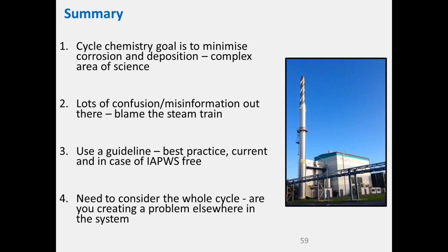There's a lot of misinformation and confusion out there, and I blame the steam train for that, but also some of that comes into what's right for one design and pressure of boiler is not necessarily right for another. So you've got to understand the cycle. And I recommend use a guideline, best practice, current, take a free one from IAPWS, or you can look at purchasing the ASME one and things like that. And you need to consider the whole cycle. By doing one thing in one location, are you creating another problem further down the path?